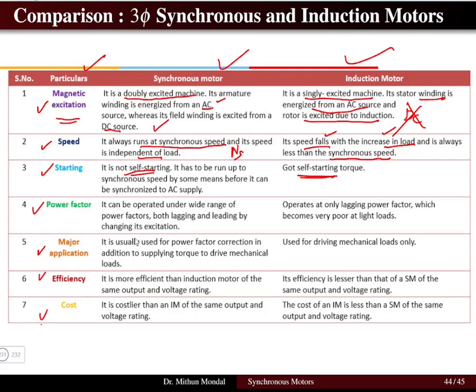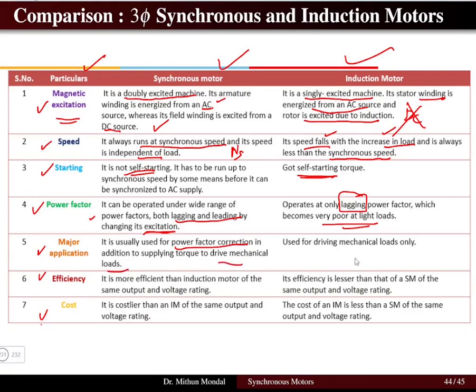Regarding power factor: the synchronous motor can operate at both lagging and leading power factors by changing the excitation — over-excited or under-excited. The induction motor operates only at lagging power factor, which becomes very poor at light load. Regarding major application: the synchronous motor can be used for power factor correction in addition to driving mechanical load, whereas the induction motor is used only for driving mechanical load.